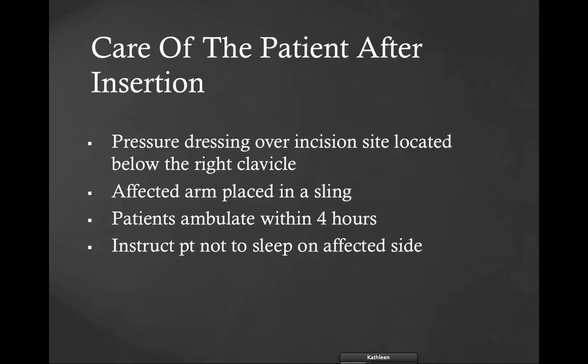When you have post-pacemaker, you will be getting 2 EKGs done, one with the magnet and one without the magnet. With the magnet, it turns off the impulse sensing device. This is to check to make sure the pacemaker is working at its preset rate, that the cardiologist put in all the right settings and it's working the way it's set. That means when you look at the EKG, you're going to see the pacemaker working 100%. It's not sensing the patient's own beat at all. It shuts off that sensing ability and just paces. What you should see is a pacemaker spike with each capture for each pacemaker impulse. Really important concept.